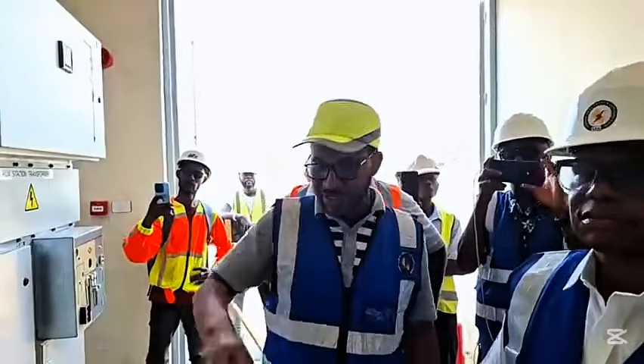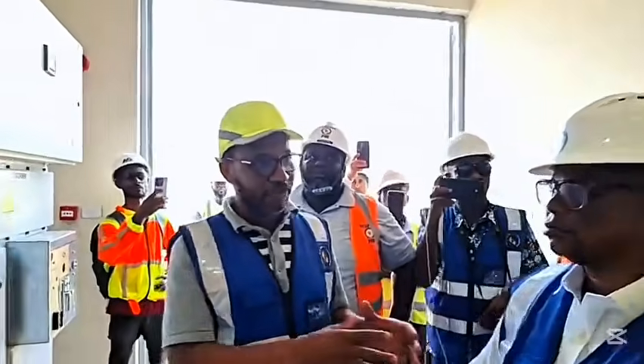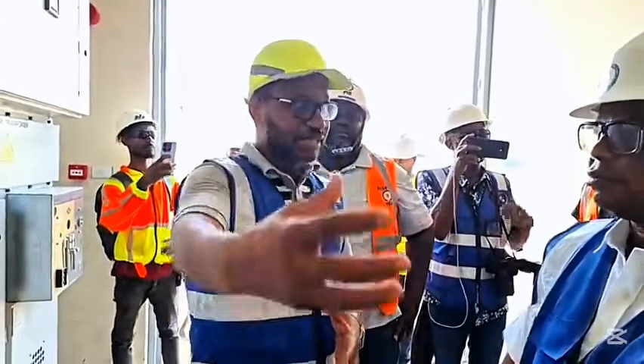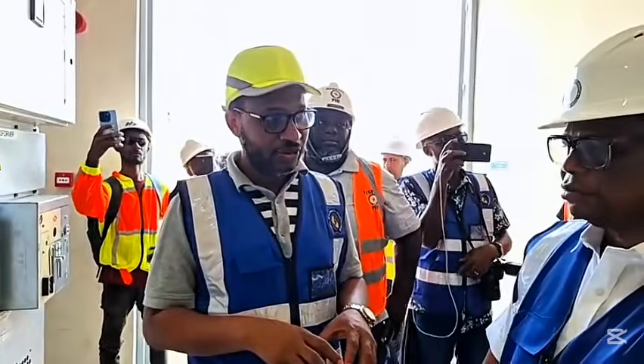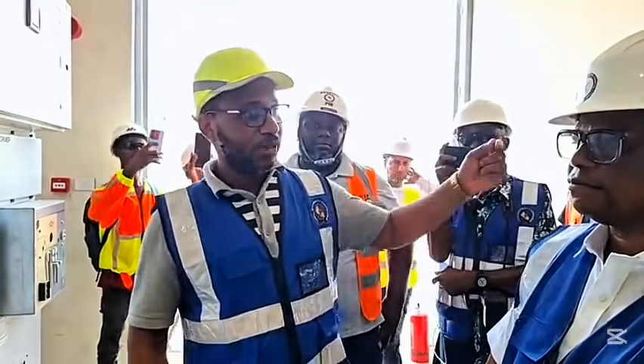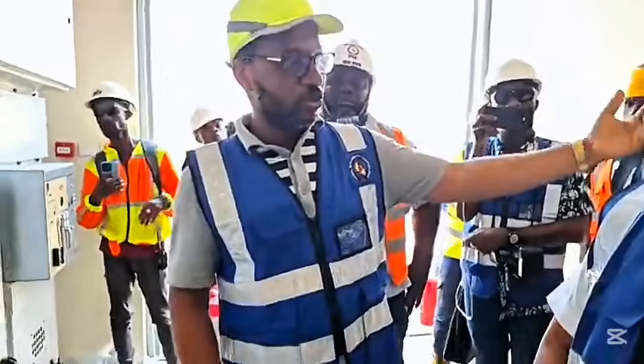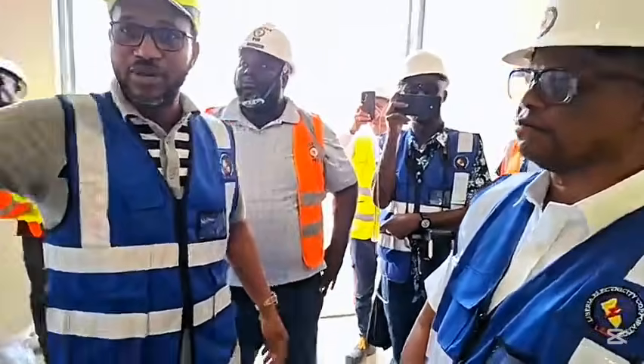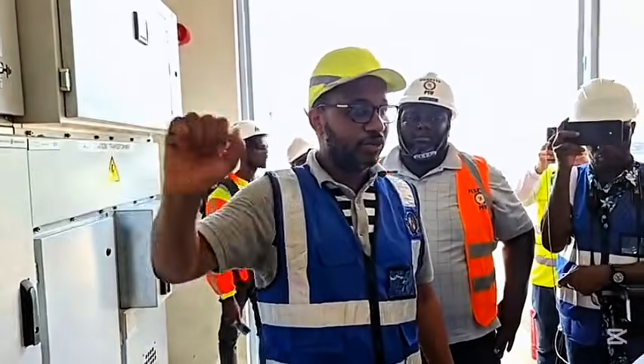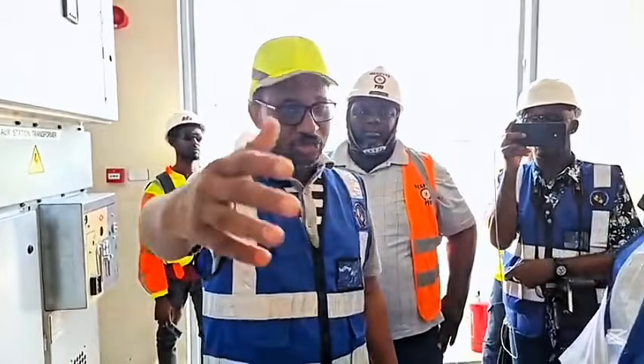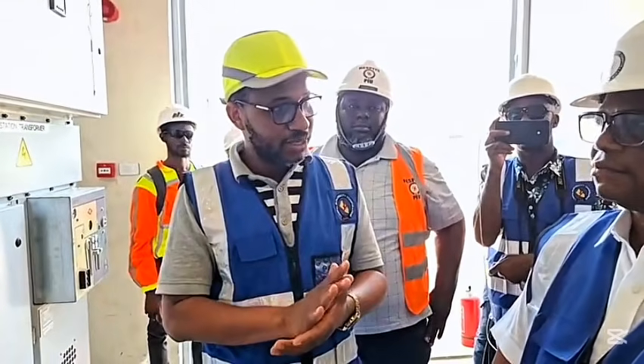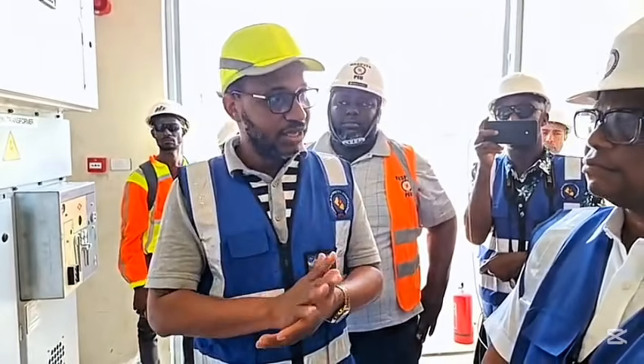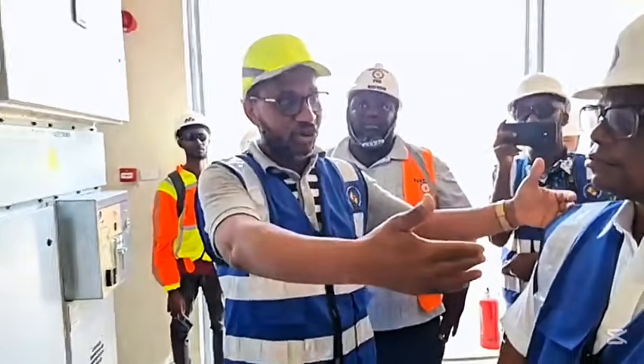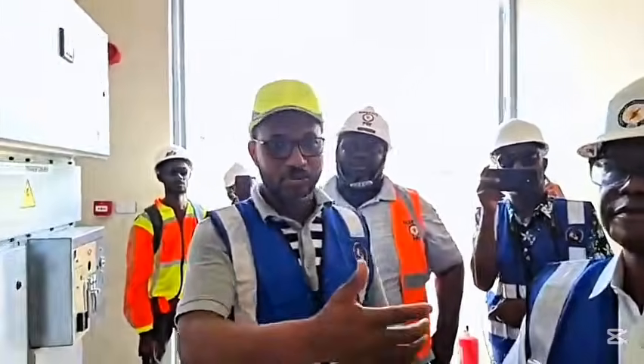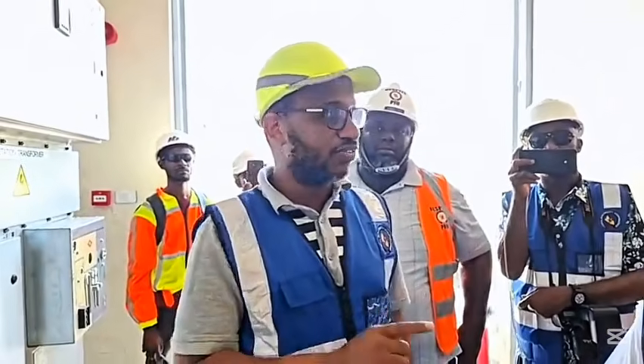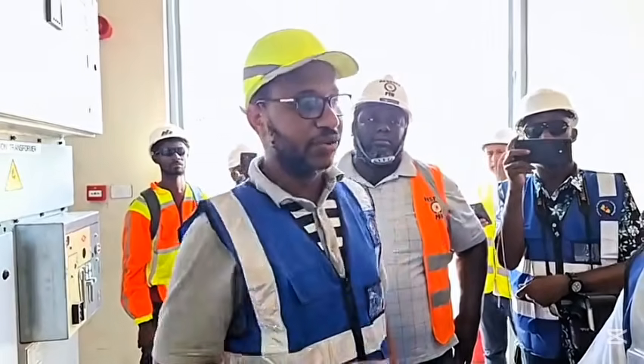For the energization of the plant, we need the presence of voltage to energize the solar plant for it to feed into the grid. So the first step is we energize backwards through the transformer, up to this point, and then carry it down. So all of this equipment is energized from the field. Once it senses the presence of voltage at the inverter point, it immediately triggers the energization of the solar plant, which in turn changes the direction of the flow of electricity towards the grid.